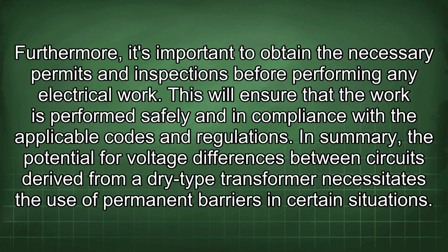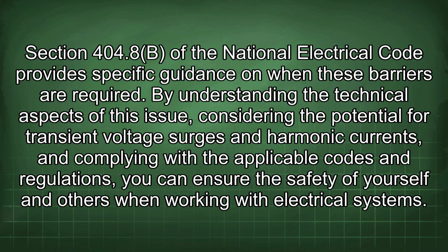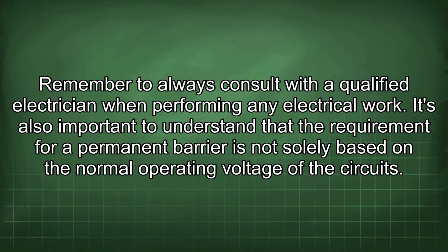In summary, the potential for voltage differences between circuits derived from a dry-type transformer necessitates the use of permanent barriers in certain situations. Section 404.8b of the National Electrical Code provides specific guidance on when these barriers are required. By understanding the technical aspects of this issue, considering the potential for transient voltage surges and harmonic currents, and complying with the applicable codes and regulations, you can ensure the safety of yourself and others when working with electrical systems. Remember to always consult with a qualified electrician when performing any electrical work.